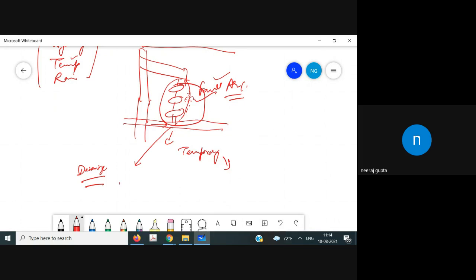There is the least possibility of restriking the arc. Because this fault is due to the flashover of the insulation, we interrupt the electrical supply for a small amount of time so that the whole path will deionize, and as a result, there is no restriking of the arc.